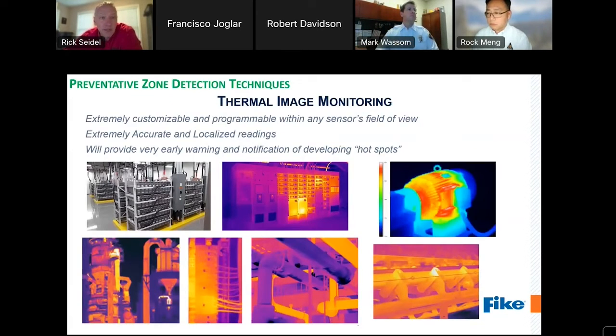One available preventative zone detection technique is thermal image monitoring. Thermal imaging has certainly come a long way in the past few years, and its applications are increasing and expanding to many realms of industry, manufacturing, and process monitoring. The software available for many thermal imaging devices allows for extremely customizable set points or alarm indications within the sensor's field of view to achieve very accurate and localized readings and reports. Thermal imaging can provide very early warning of developing hotspots or overheats so that your response protocols can begin as quickly as possible.